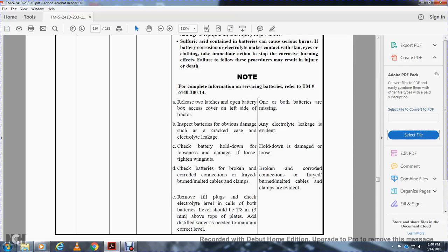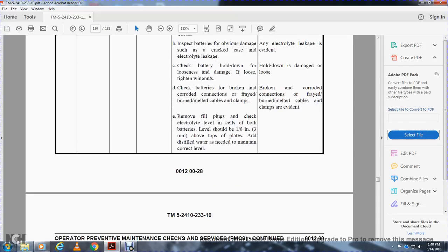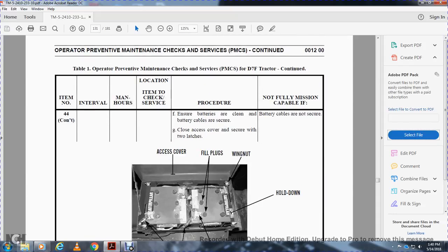Remove the fill plugs and check the electrolyte in the cells of the batteries. The level should be 1/8 of an inch above the top of the plates. Add distilled water as needed to the correct level. Ensure the batteries are clean and the battery cables are secure. Non-mission capable if the battery cables are not secure. Close the cover and secure the 2 latches.